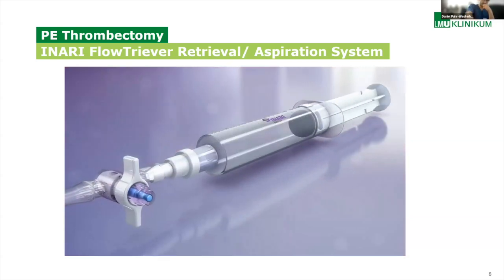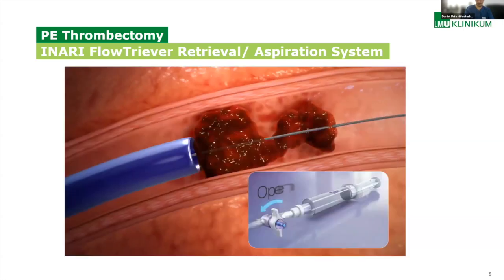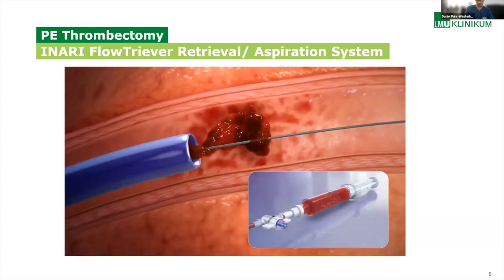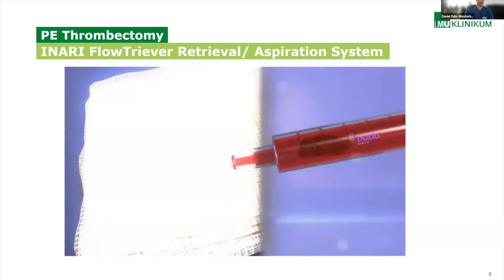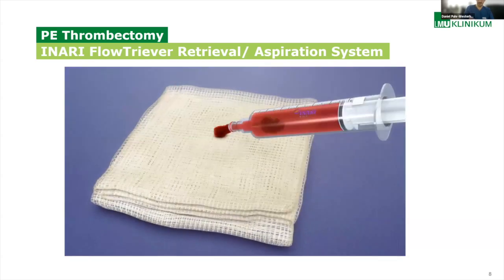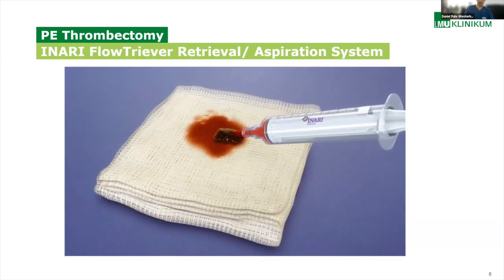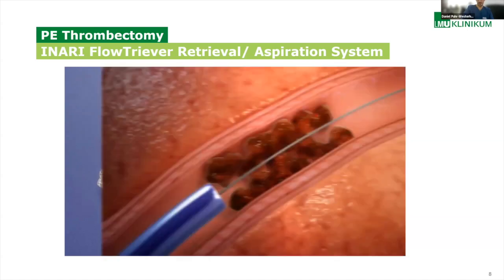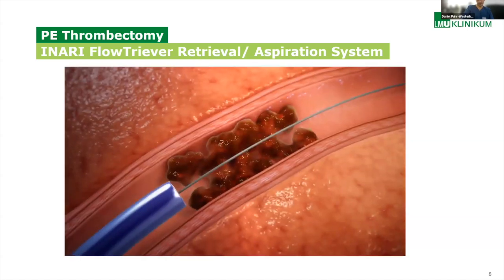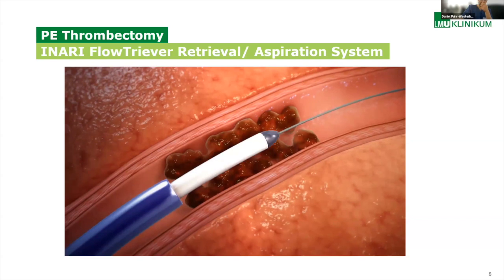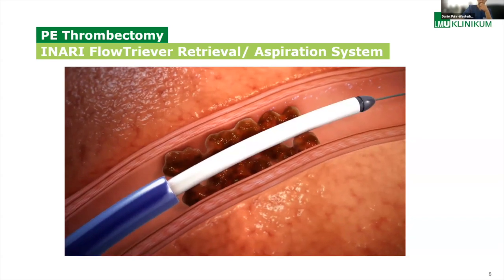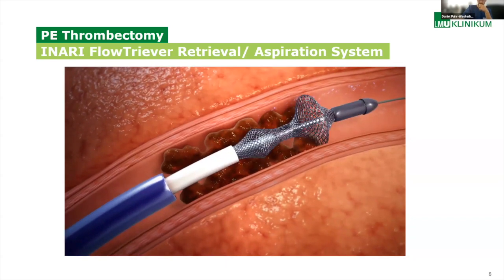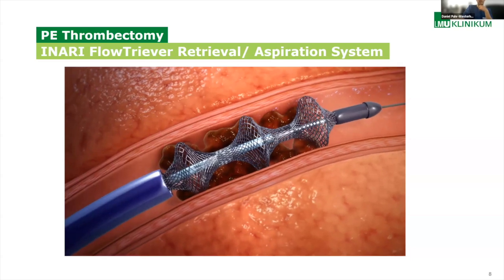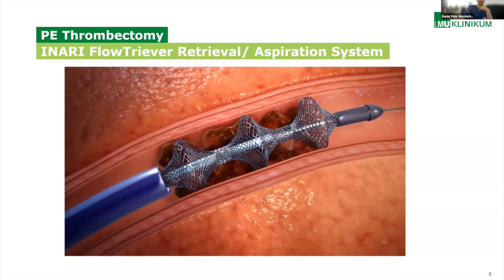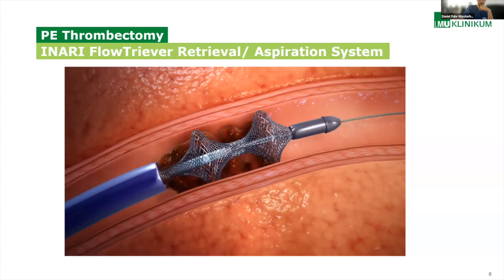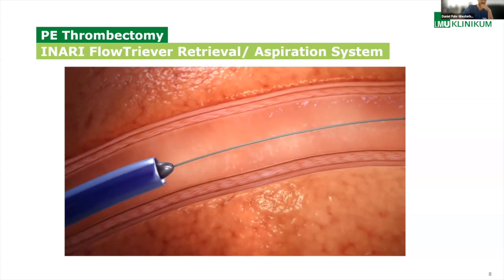First, the stopcock is closed. We can lock the syringe and then open the stopcock that allows immediate suction, and therefore the clot can be retrieved from the pulmonary circulation. This is how it looks like in principle. Sometimes the nitinol discs can also be used, but as I said before, most of the time, if it's like a quite recent thrombus, it's perfectly fine to just use the FlowTriever. It's usually enough.